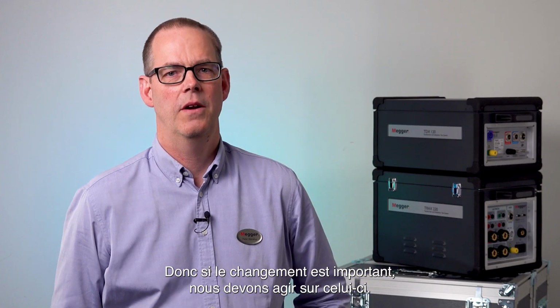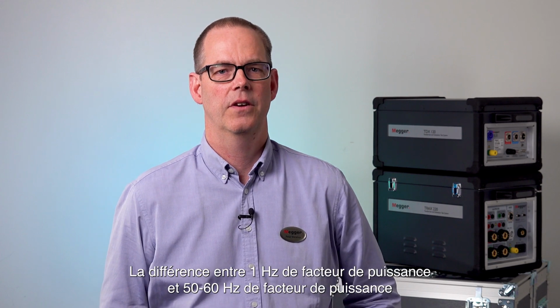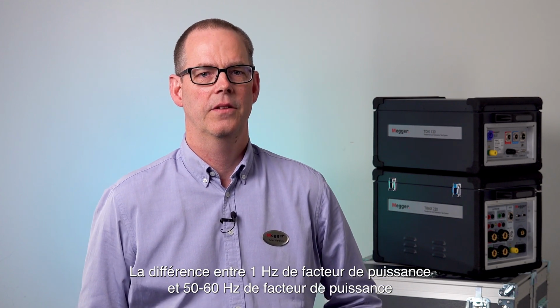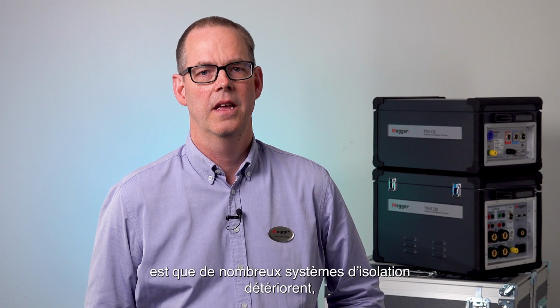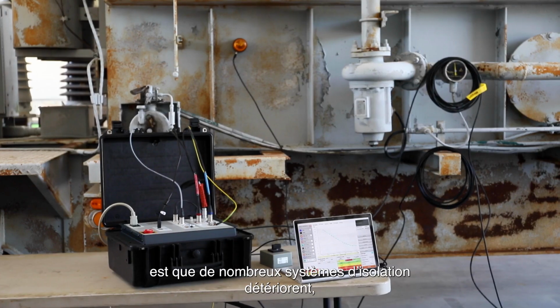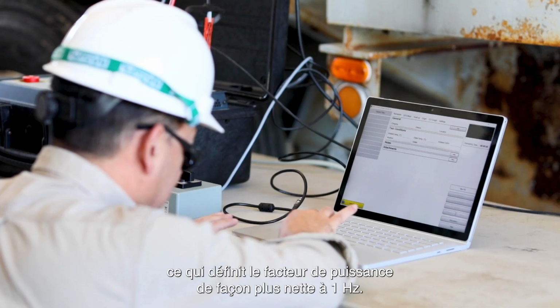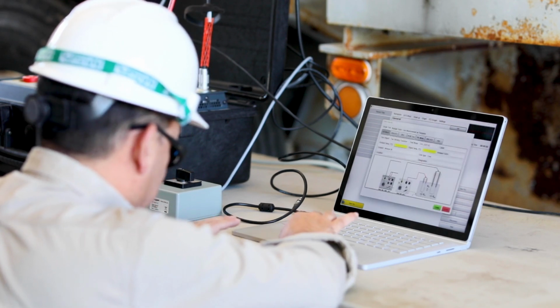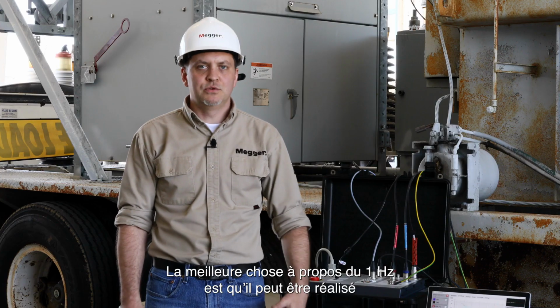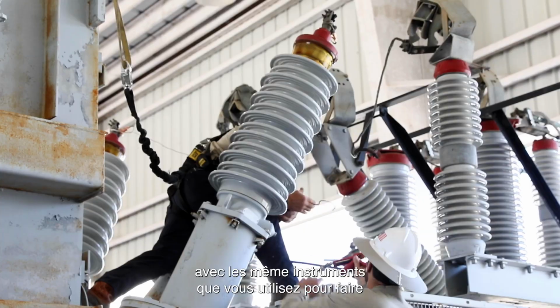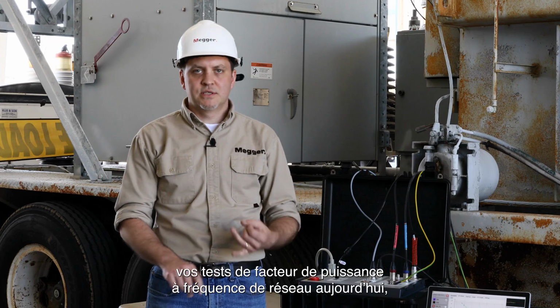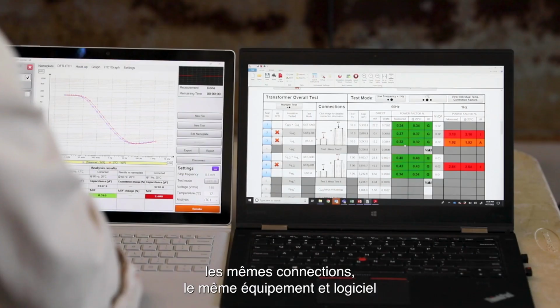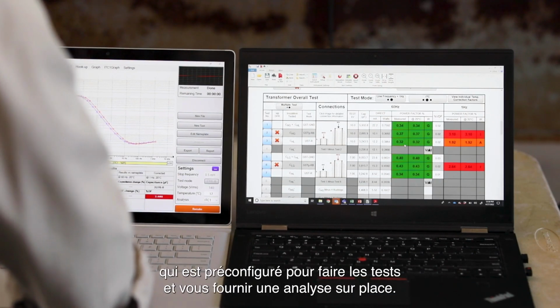The difference between 1 Hz power factor and 50-60 Hz power factor is that many insulation systems deteriorate, which changes the power factor more definitely at 1 Hz. The best thing about 1 Hz is that it can be performed with the same instrument that you use to do your line frequency power factor testing today. The same connections, the same equipment, and software that's pre-configured to do the testing and provide you analysis on the spot.